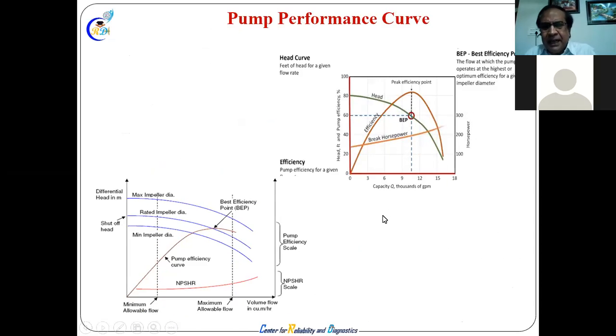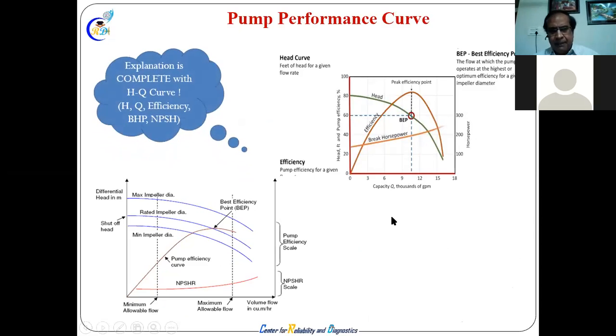So these are the different curves: the head and capacity curve, the HQ curve, which I was telling you. This is the efficiency curve. This is the head capacity. This is the brake horsepower, increasing over the capacity, and here is the best efficiency point. This is the point where it will run best. Efficiency is maximum, and on the HQ curve, whichever side you go, you are compromising the saving in energy. Okay, because this energy curve is there.